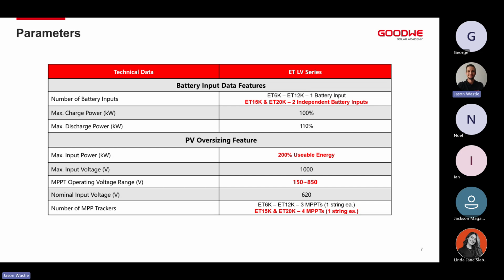The MPPTs on the ETLV series are also all independently controlled. So on the 12 kilowatt units, we have 3 MPPTs with 1 string each, with 1 input each, and the 15 and 20 kilowatt units, 4 MPPTs with 1 string each. So every single connection, MPPT string or PV string is independently monitored and controlled on the system, meaning you can have 4 different string lengths, 4 different roof orientations, 4 different angles or tilt angles. The system can operate all 4 of them independently.